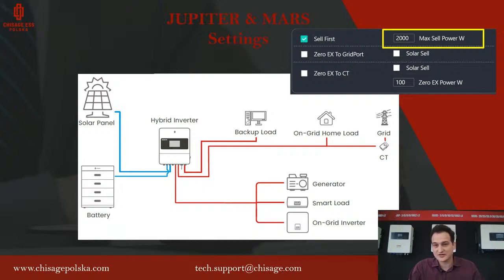So what I have, I sell. Second mode is zero export to grid port. That means that the inverter will stop power on the grid port of the inverter. So it doesn't support the on-grid home load and doesn't sell to the grid. So the inverter will charge the battery, will secure the backup load and the smart load, but does not support the on-grid home load, does not support the grid. But we can pick solar sell. Solar sell means that if I have enough power to support the backup load, charge the battery, run the smart load, etc., I can sell.